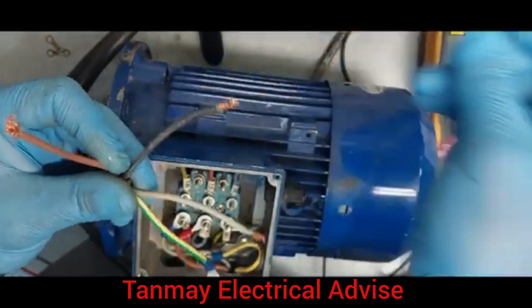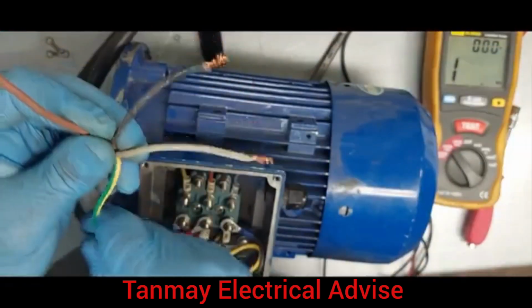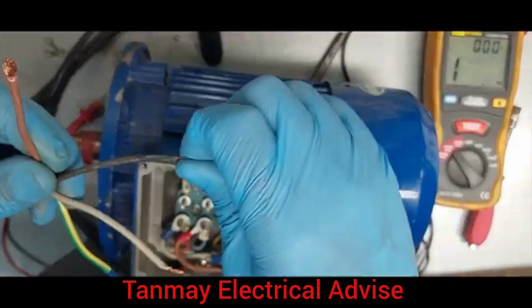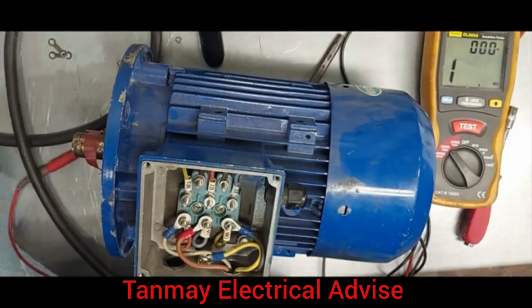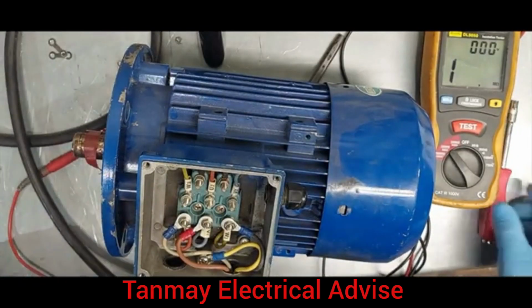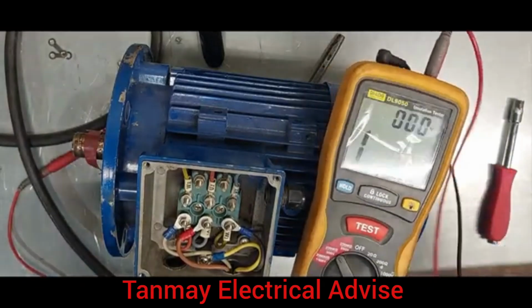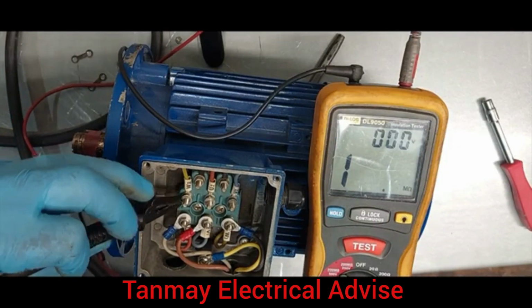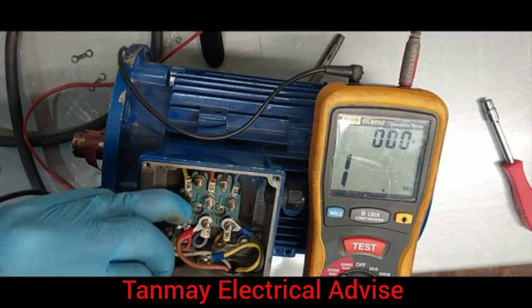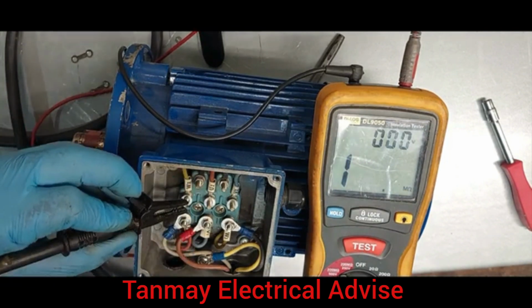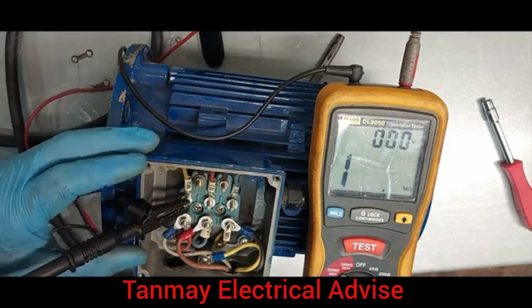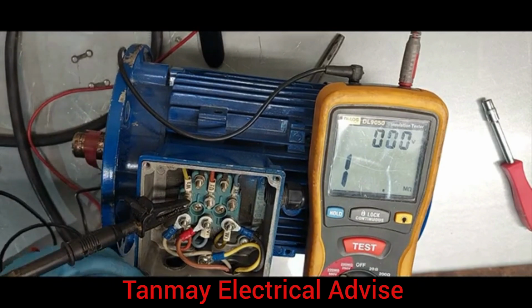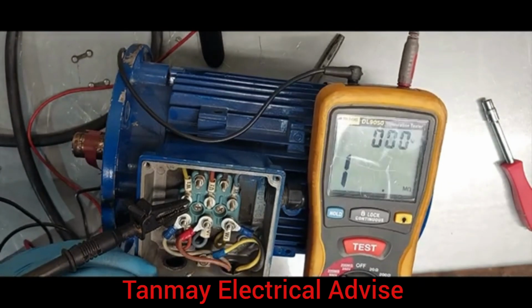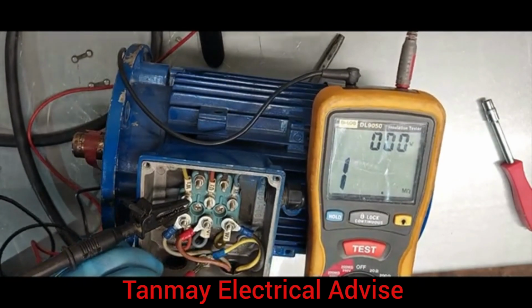Make sure that the insulation is all right, because high voltage and corrosion can cause the insulation of the motor, the insulation of the cable, and the insulation of the winding to deteriorate. So if we put it on U2 here, we can test it to make sure there's no leakage to earth. We test it between each of the windings and the chassis.